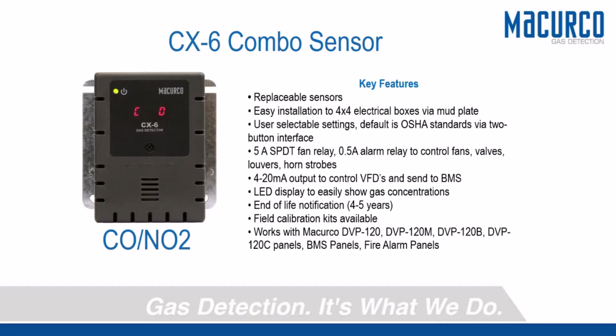But it's 2-in-1. You've got 2 sensors in one. It's reading 2 different gases. It's giving you 2 different signals, whether you want to focus on the CO or the NO2. And you can send that back to a fire panel. You can send it back to a Macurco panel or a BMS system, no problem. You have a 4 to 5 year life on this with field replaceable sensors. So it's big on the service side for calibration and testing.